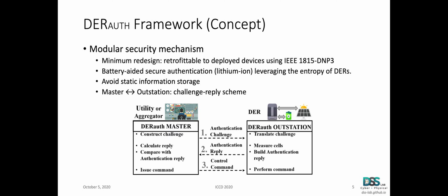Our framework, named DERAUTH, secures the measurement and control command data issued to DERs. It provides a security extension that can be retrofitted to any battery storage enabled grid asset which uses DNP3 with minimum redesign requirements, serving as an authentication layer on top of the DNP3 protocol stack.